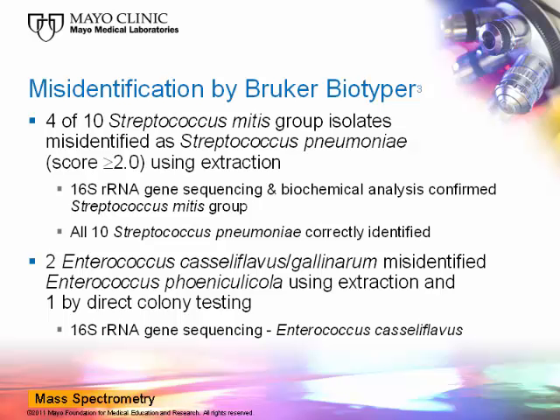There were some limitations. Four of ten Streptococcus mitis species group isolates were misidentified as Streptococcus pneumoniae using extraction, though all ten Streptococcus pneumoniae were correctly identified. The difficulty in distinguishing closely related species may be due to similar composition of ribosomal proteins, the main target for MALDI-TOF mass spectrometry. Two Enterococcus casseliflavus/gallinarum were misidentified as Enterococcus phoeniculicola using extraction. Correct identification of Enterococcus casseliflavus was reached when the library was updated, which we confirmed using preparatory extraction.